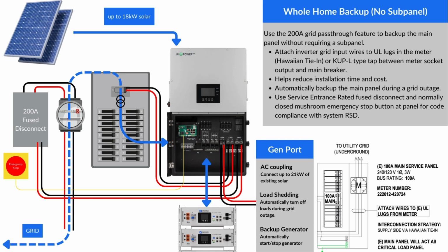Now, if you're looking at this diagram and you're wondering, how is this going to meet code compliance for safety and rapid shutdown? The way this works is by having an emergency stop mushroom button, the 200 amp fuse disconnect, and the main breaker in the main panel. By pushing the emergency stop button, you will not only shut down the inverter, but also the batteries. You'll also turn off the panels by doing so. You'll cut the AC output from the inverter to the main panel. By turning the 200 amp fuse disconnect off, this will cut grid energy from the main meter to the inverter. You turn off the main breaker to the panel, and this will cut all circuits to the home.